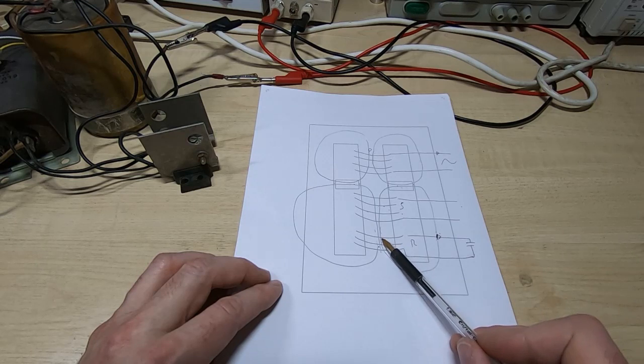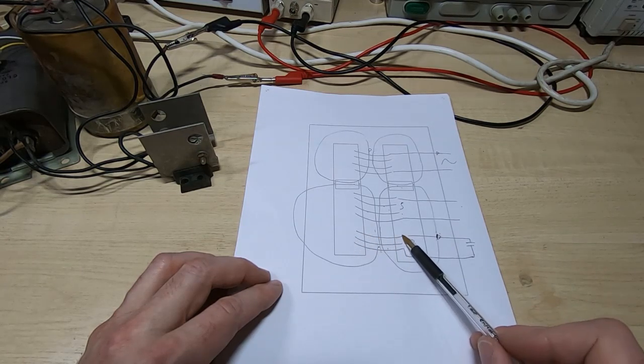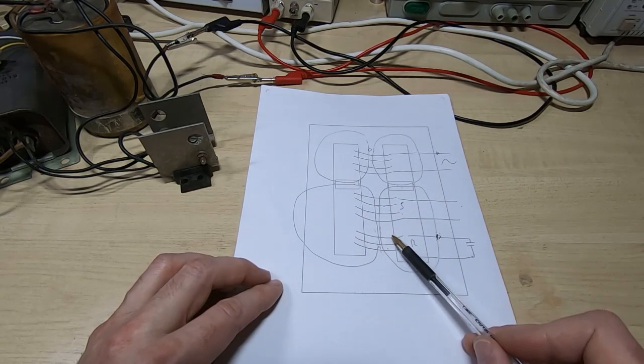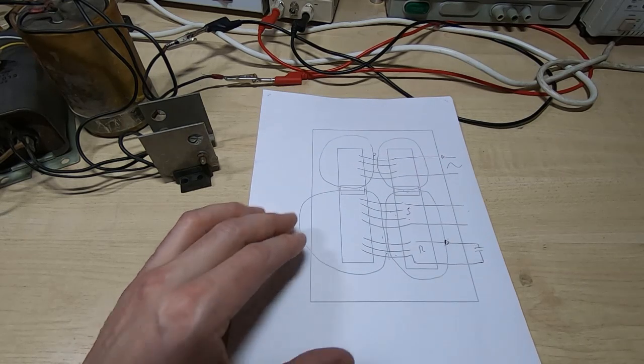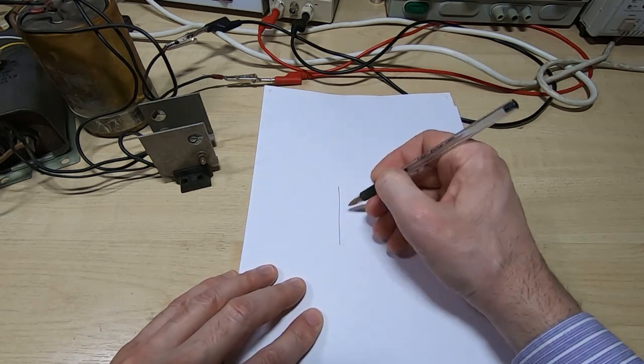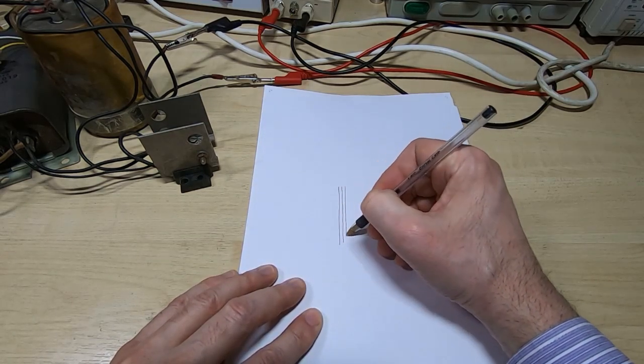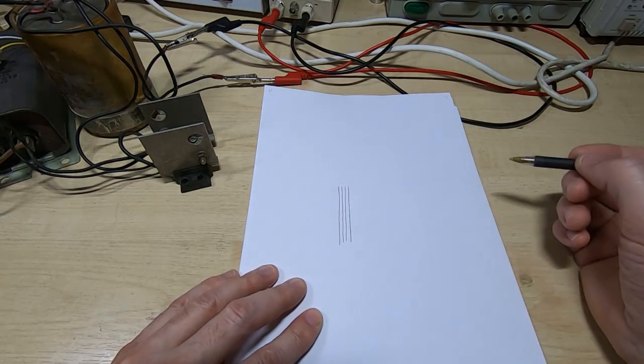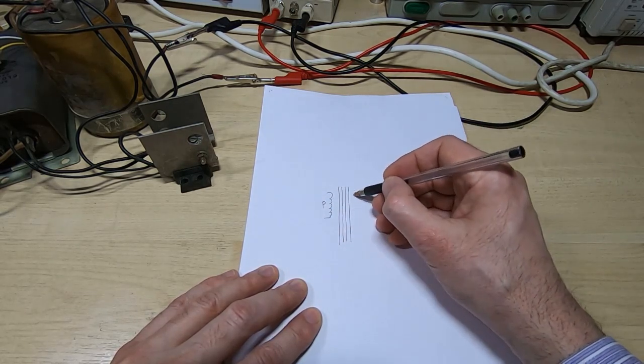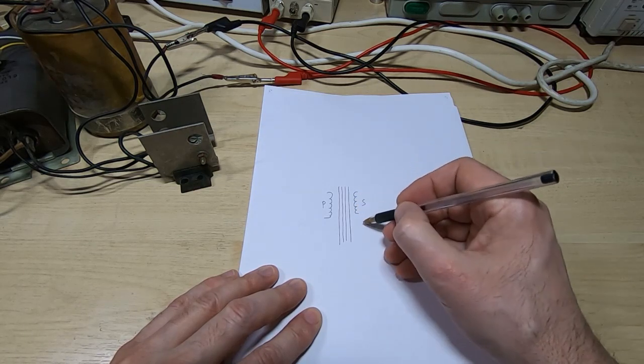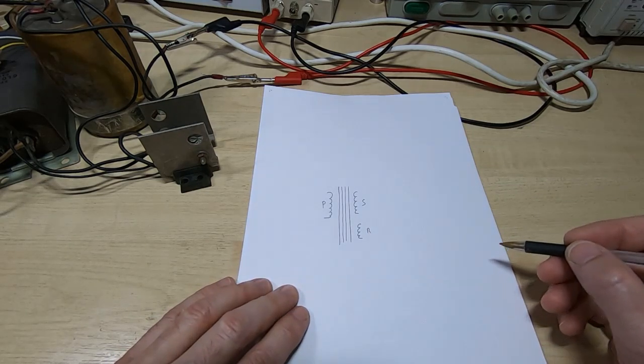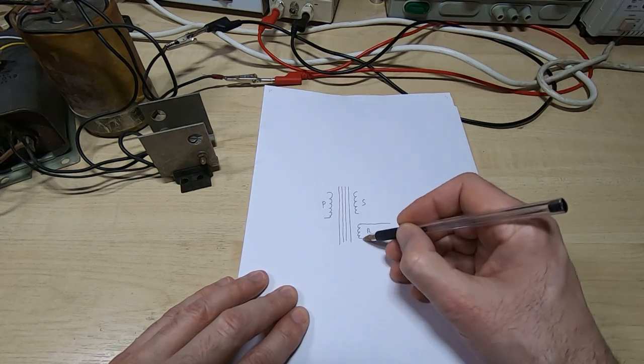And the way this is achieved is through the use of a third winding, which is the resonant winding. So if we take this diagram and I redraw it as a schematic representation rather than a physical representation, what we end up with is a transformer. So we have the core. I'll ignore the shunts for now. They're not important for this particular part of the discussion. We have the primary winding on one side, we have the secondary, and then we have the resonant winding. And as I said in the previous video, the only thing connected to the resonant winding is a capacitor.